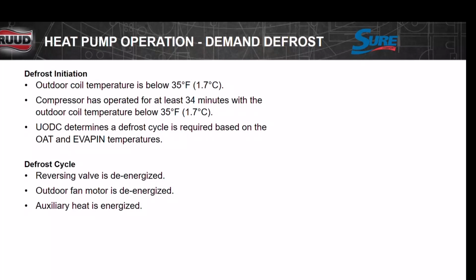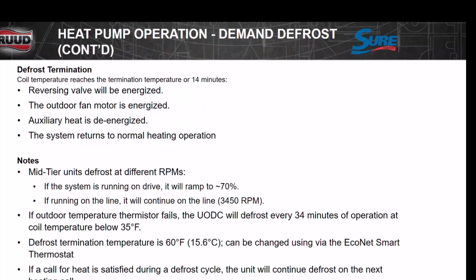Defrost, this is what happens on defrost. The outdoor temperature is below 35 degrees, the compressor has operated for at least 34 minutes, and the outdoor temperature is below 35 degrees, that's when we're going to get defrost. That's when it's going to initiate. If the outdoor temperature is 35, but it hasn't run for 34 minutes, it's not going to even look at it, right? So basically on a defrost cycle, the reversing valve is de-energized, the outdoor fan motor is de-energized, and auxiliary heat is energized. Termination is just a reverse cycle. Reversing valve energized, the outdoor fan motor energized, and electric heat is de-energized. And it returns back to normal heat.